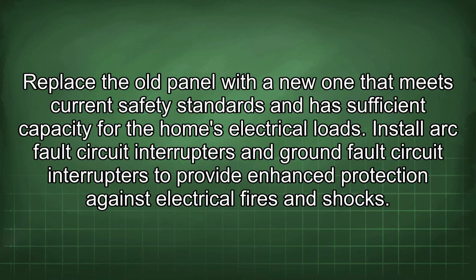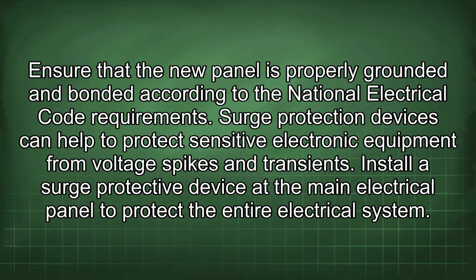Install arc fault circuit interrupters and ground fault circuit interrupters to provide enhanced protection against electrical fires and shocks. Ensure that the new panel is properly grounded and bonded according to the National Electrical Code requirements. Surge protection devices can help to protect sensitive electronic equipment from voltage spikes and transients.